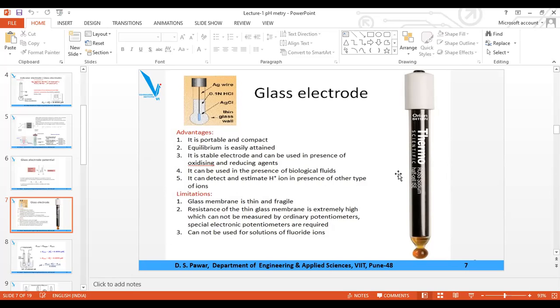And you can determine H plus ion in presence of other ions. Mainly, even though the glass electrode is applicable for other ions, it is used in the pH meter to find out the concentration of H plus ion in presence of other ions. It is compact, portable, and can be used in strong oxidizing and reducing medium. It can be used even if algae and fungi are there in the water sample whose pH is to be determined. It can be used for pH range from 2 to 10.